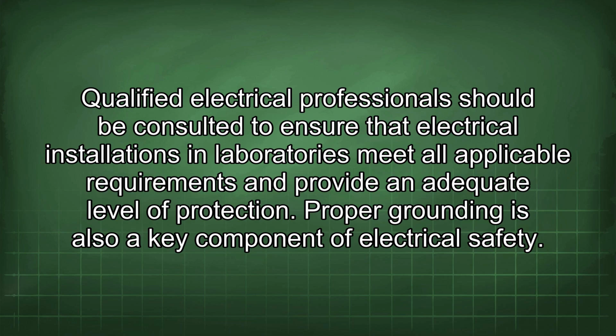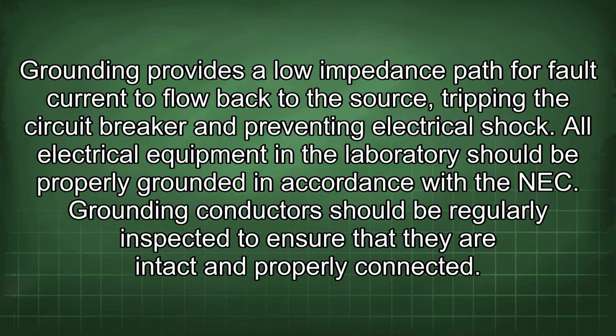Proper grounding is also a key component of electrical safety. Grounding provides a low impedance path for fault current to flow back to the source, tripping the circuit breaker and preventing electrical shock. All electrical equipment in the laboratory should be properly grounded in accordance with the NEC. Grounding conductors should be regularly inspected to ensure that they are intact and properly connected.